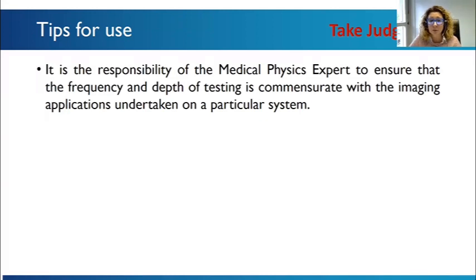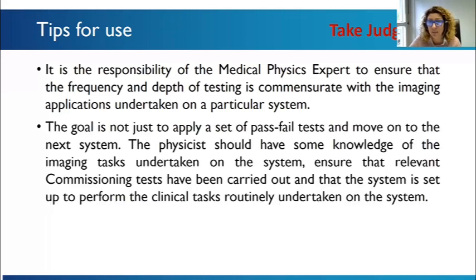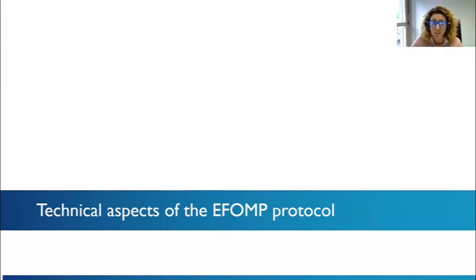So it is, in the end, the responsibility of the medical physics expert to ensure that the frequency and depth of testing is commensurate with the imaging application undertaken on a particular system, and is not just about applying a set of pass-fail tests and moving on to the next system. The idea of this protocol is also that the physicists gain knowledge of the equipment and how it works, based on the imaging task undertaken with the system. I'm done with the first part of the presentation, and I leave the floor to Nick.